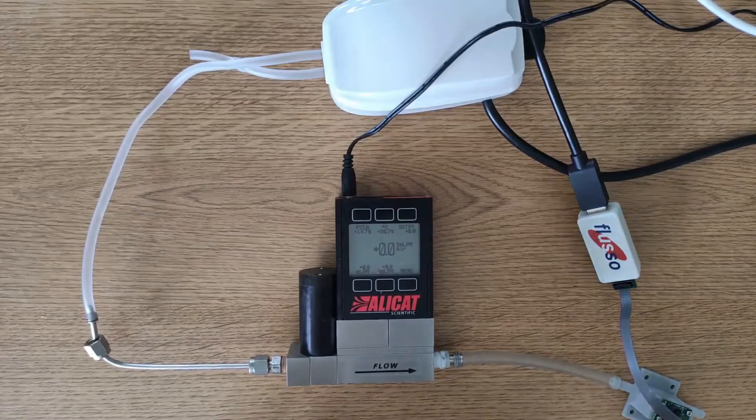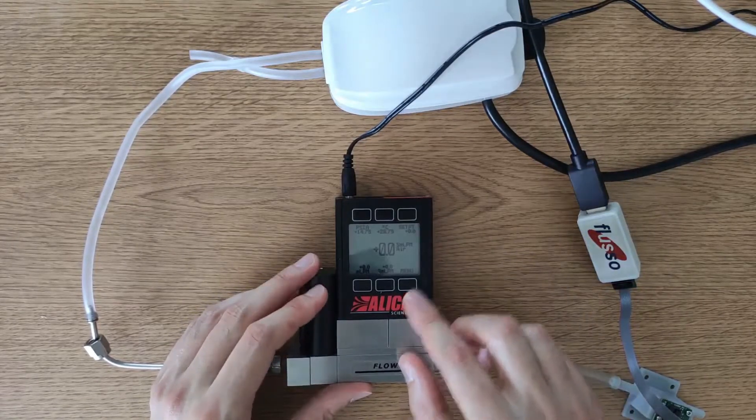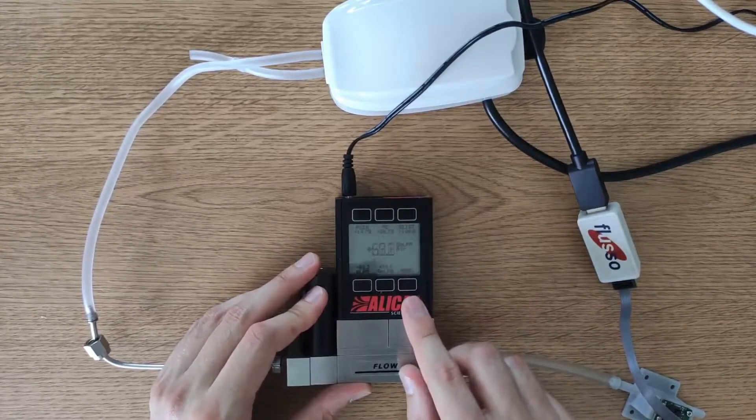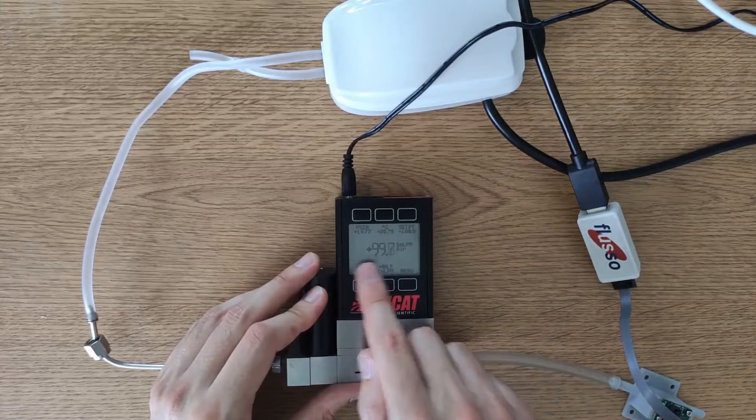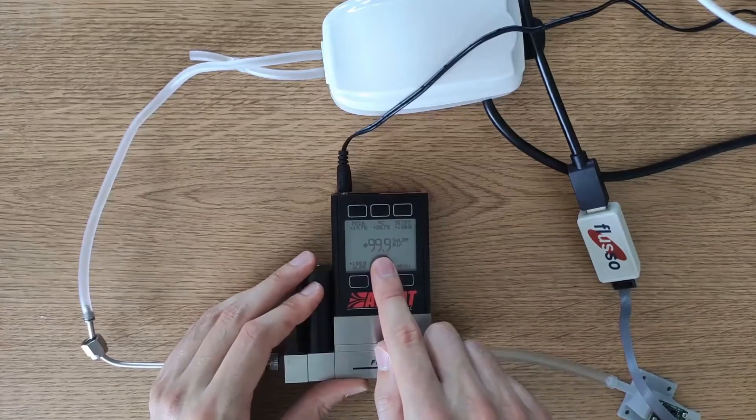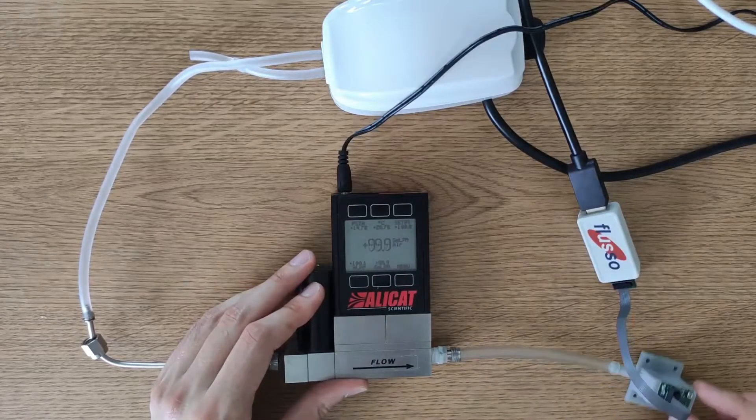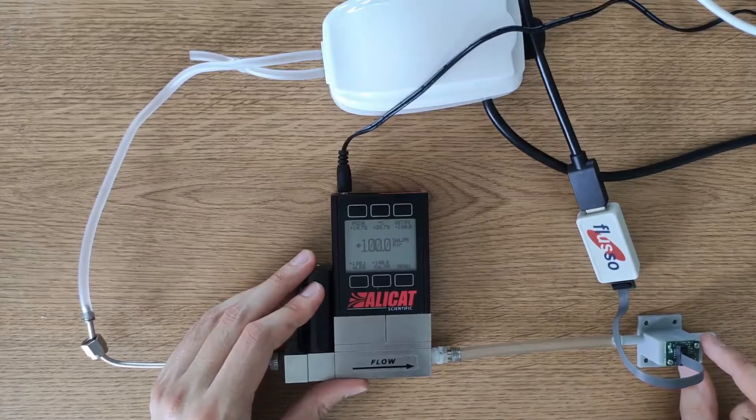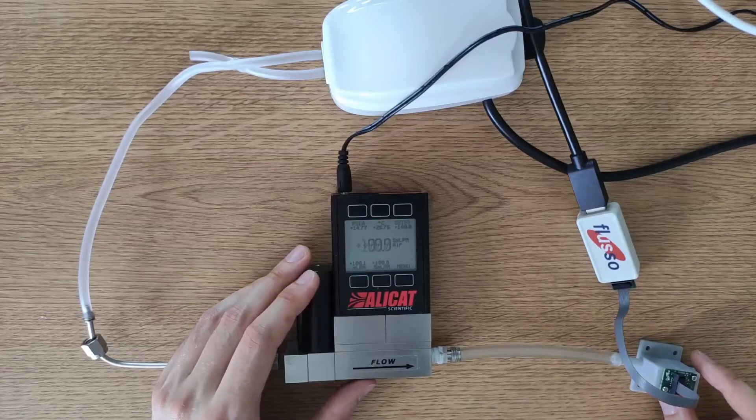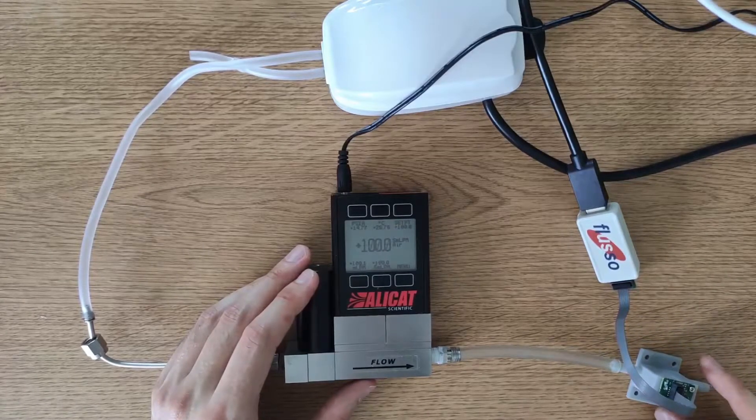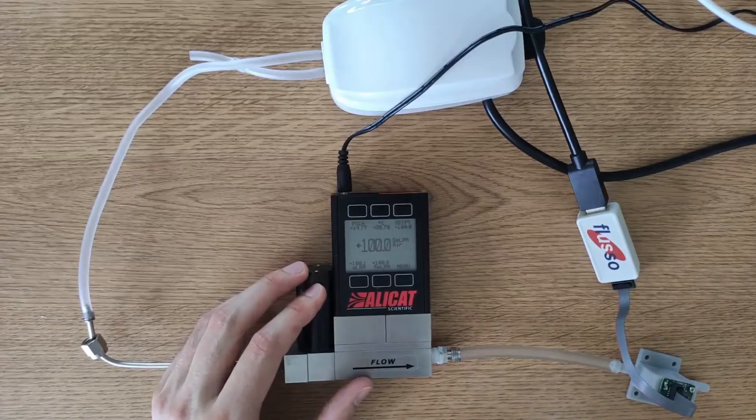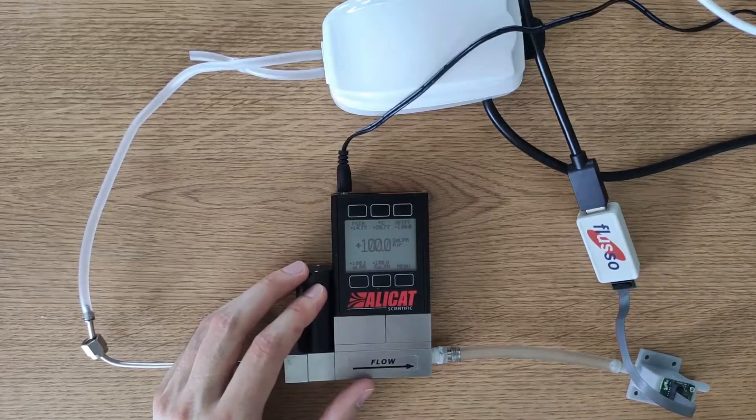Once we have the fish tank pump running we can set our MFC to some value, let's say 100 SCCM, and check that we get 100 SCCM passing through our mass flow controller and therefore also passing through our FLS110. If you've got to this stage then your fluidic setup is done and all that remains now is to set up the FLS110 GUI software. So we'll do that now.